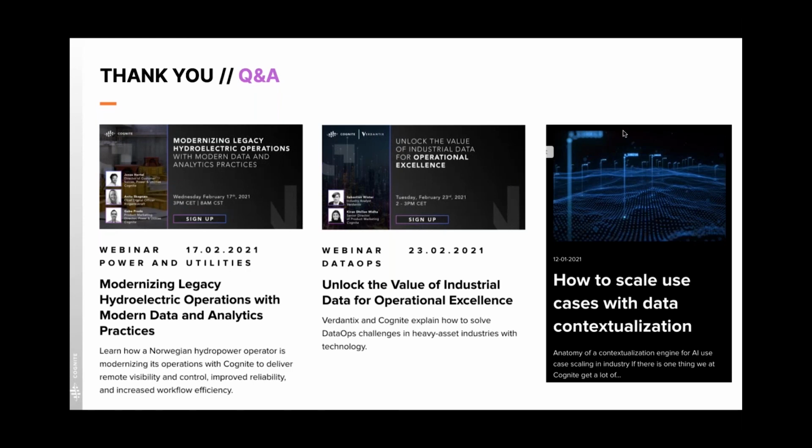Yeah, so it depends on your definition of real-time first, because in the OT domain, I would not use CDF to do surge protection in compressors, where you have to respond in fractions of milliseconds, because CDF is a cloud-based system, so you need to get your data from the actual equipment to the cloud, do some processing, and back.